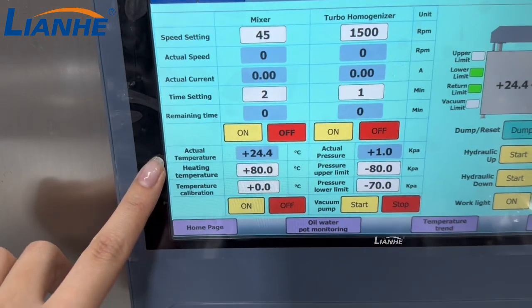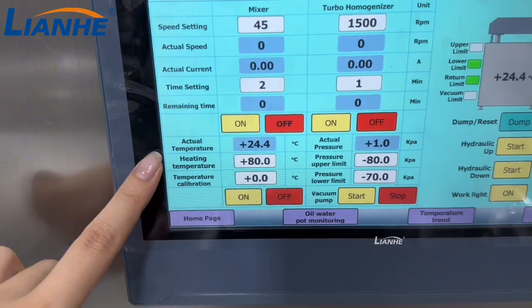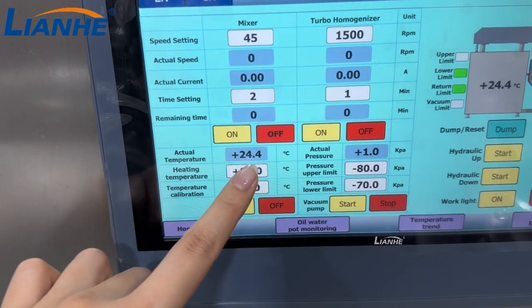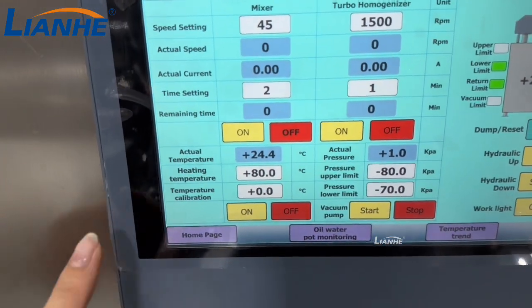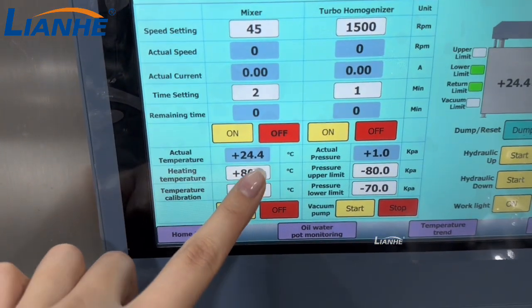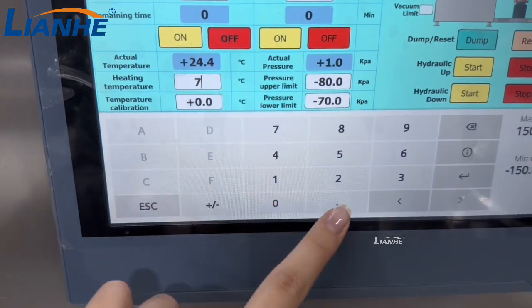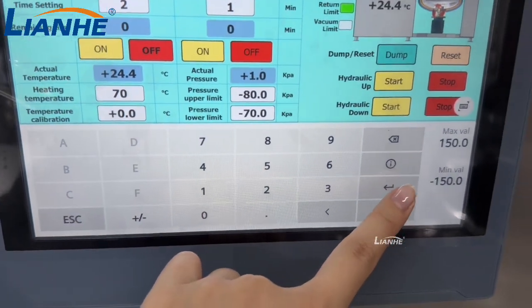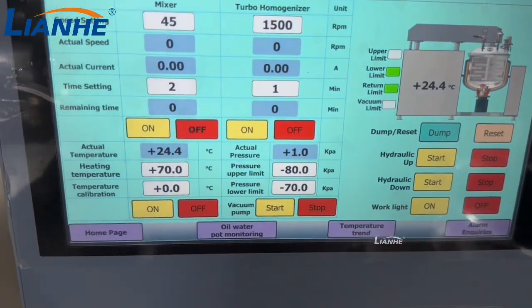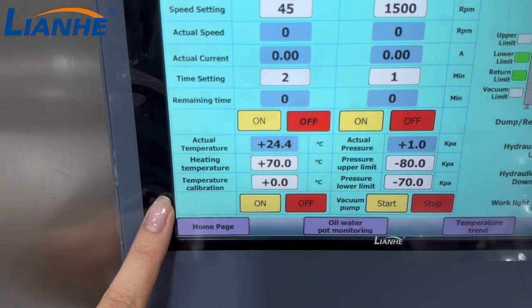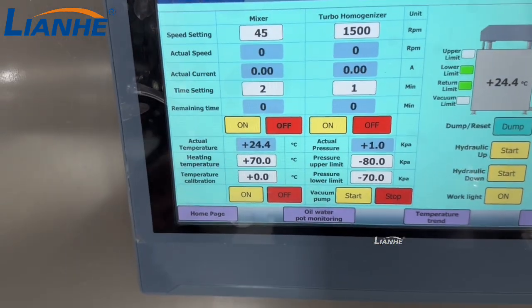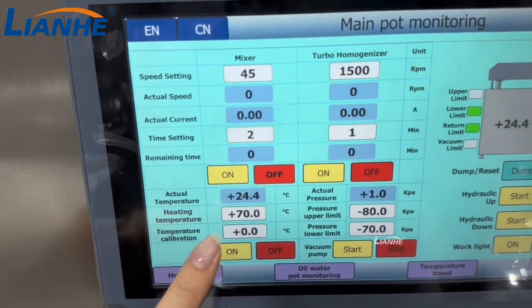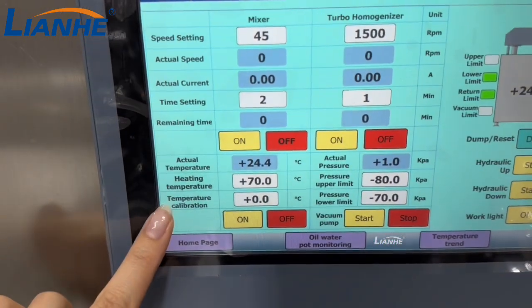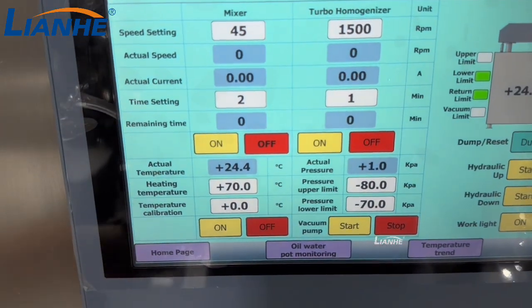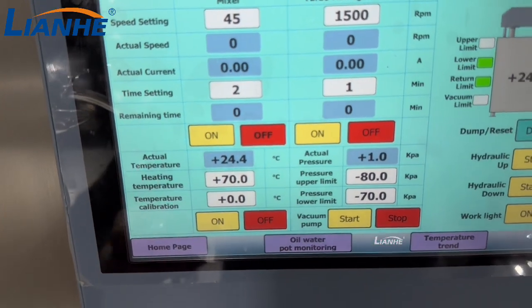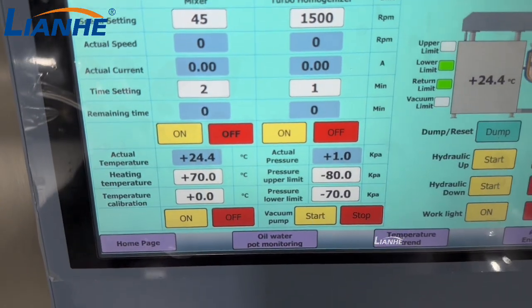And then this is the heating function. This is the actual temperature display here, now 24.4 degrees Celsius. And the heating temperature we can set here. Like if we want 70 degrees, set it here. And then this is the temperature calibration. When you find that the temperature is different between what you set and what you test, you can choose this temperature calibration to adjust the temperature so that it makes them the same. And then this is the on and off of the heating function.